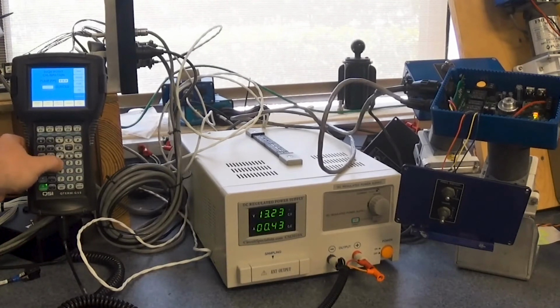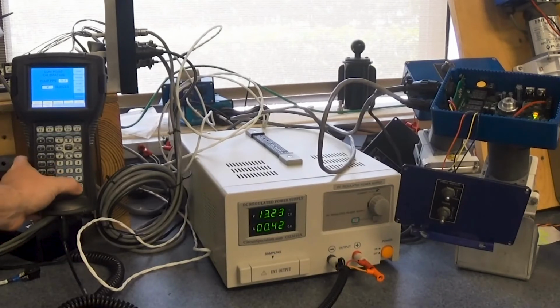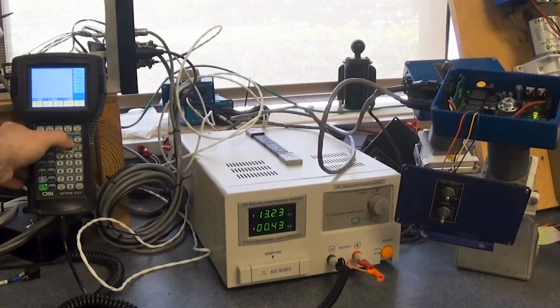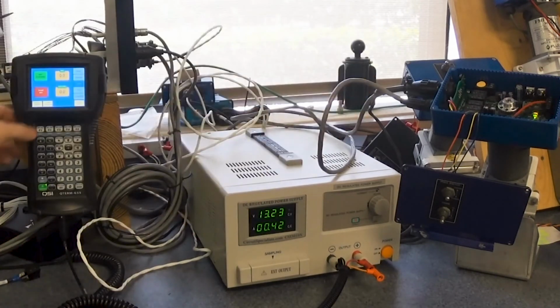So we'll type in our values again. Put in 16 ounces, for example. Then we'll put in 7.9. And then we'll put in 4 for our low. Calibration slope looks good as well. But now that we've recalibrated with the lens cleaned up, when we throw it into manual spray, for example, the pump sprays at the appropriate rate, and we're seeing our flow rate that we're trying to target.